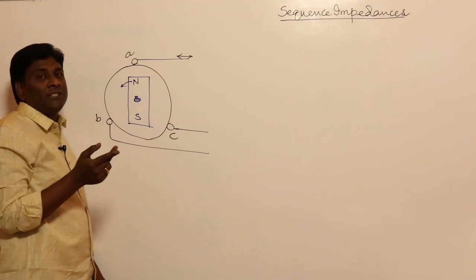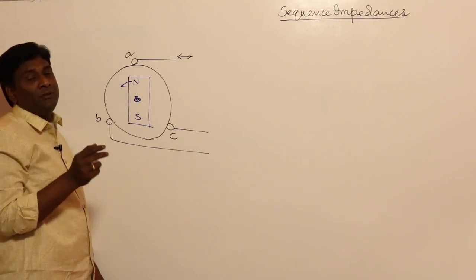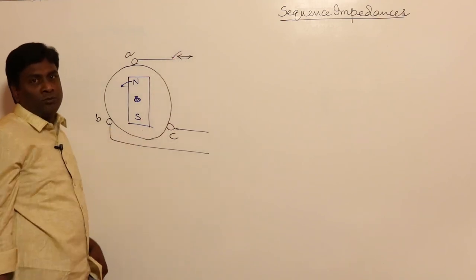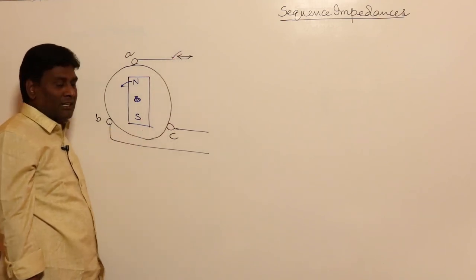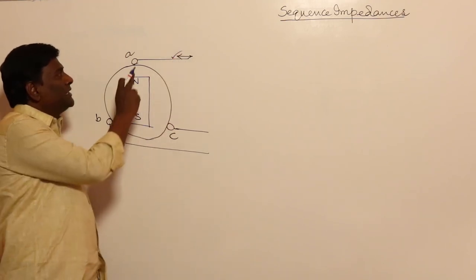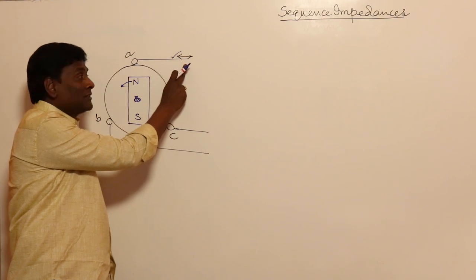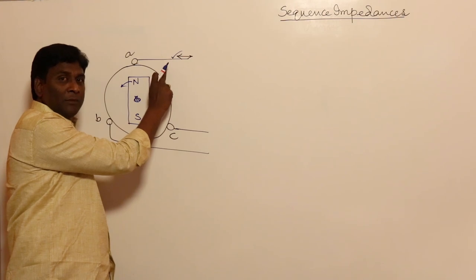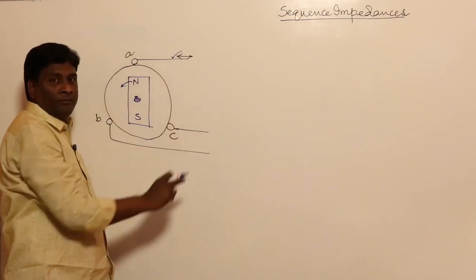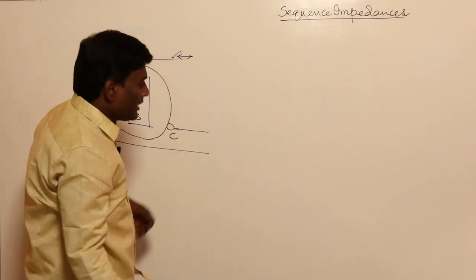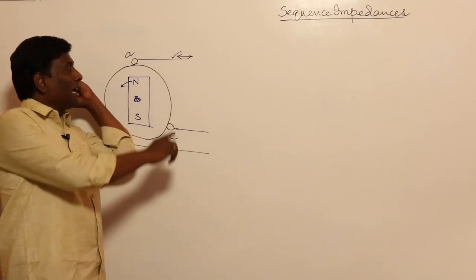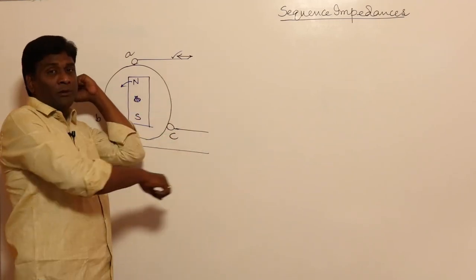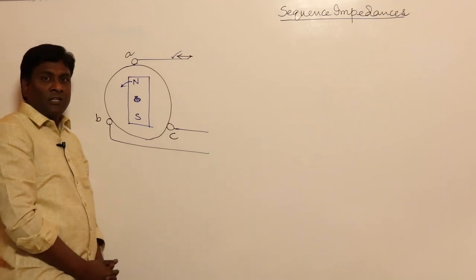Now if you think of negative sequence currents — what is negative sequence? It is A, C, B phase sequence. If negative sequence currents flow, the rotating magnetic field (RMF) created in the armature rotates in the opposite direction. So my rotor is rotating in one direction, but the RMF created because of negative sequence currents will be in the opposite direction.